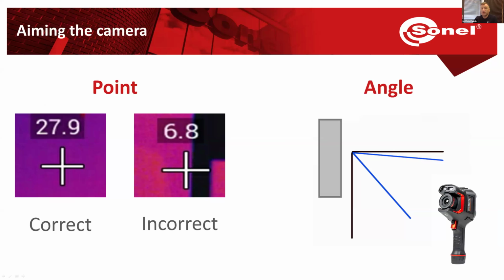Further on about pointing the camera: we need to point it at a certain angle towards our object. If we point it straight at 90 degrees, we'll just see our own reflection - the reflection of the thermal imaging technician - so we don't want that. On the other hand, if the angle is too wide, we won't check the temperature of the object but mostly see reflections from other sides. These are unwanted situations.